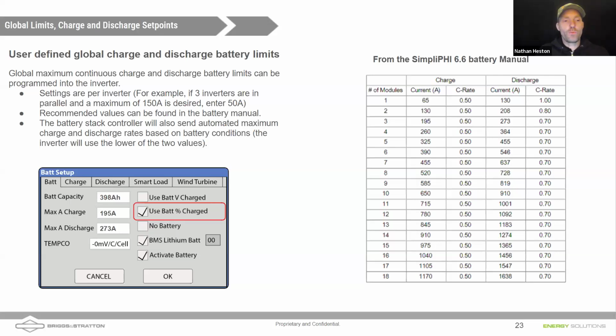Now, if you've got a larger bank of batteries, if we have 4 or more batteries, the max value that the battery can take is greater than the value that the Sol-Ark can do. So you can just set the Sol-Ark at the max value. What are the maximum values you can put in there for charge and discharge, Daniel? 273 amps if you have just the single inverter. And that's notable. A single stack of 3 6.6 batteries can handle that 273.